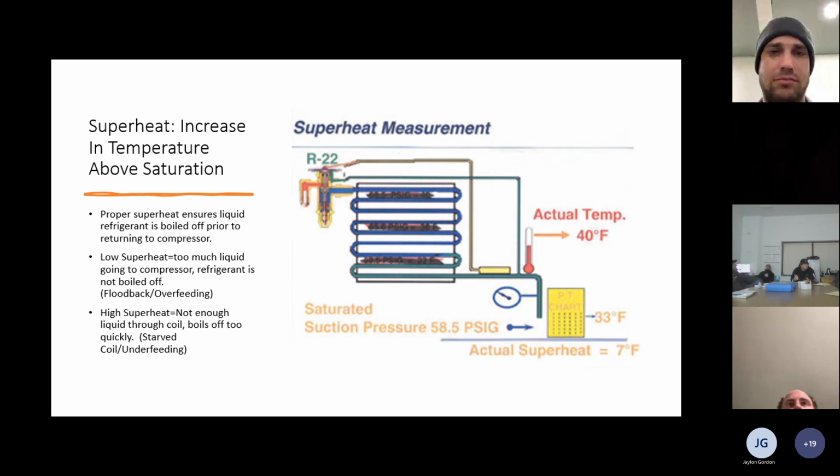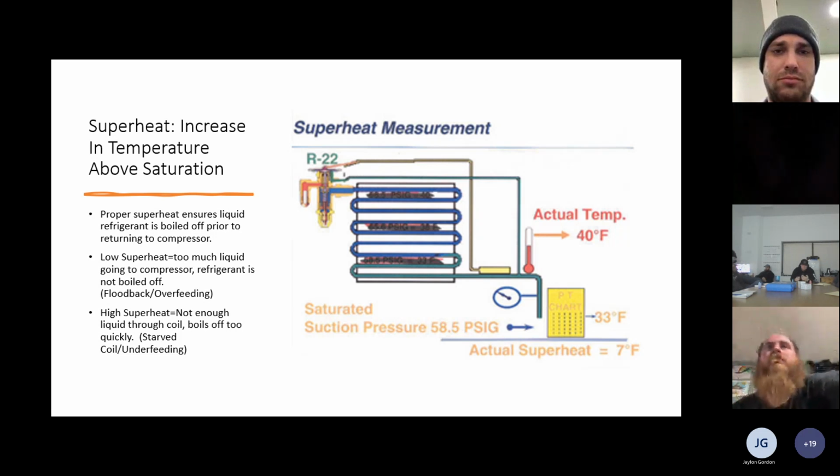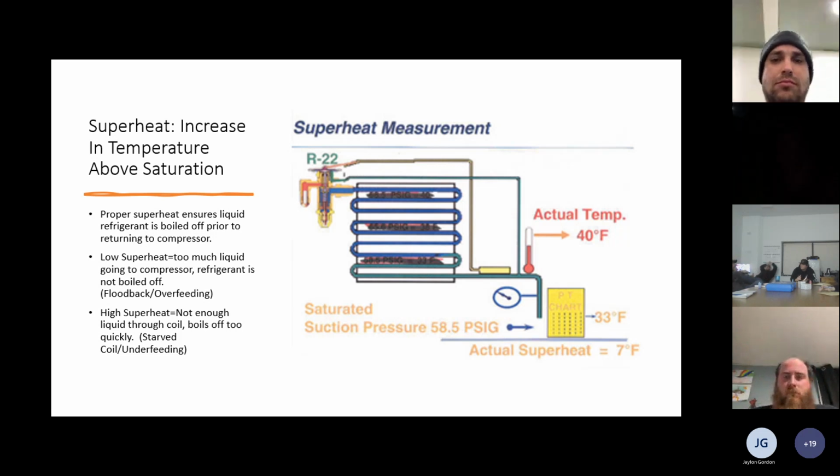Plus with the FieldPiece, there are different apps you can use; you don't have to use the FieldPiece app. I'd get another one that's more accurate. So I would highly suggest learning it first with analog gauges, like Chris said, and watching what your temperature is doing. That way you'll be able to see when your expansion valve is closing and opening, because you'll watch your temperature rise, and when it opens, it drops. That lowest number is when you do your calculation.